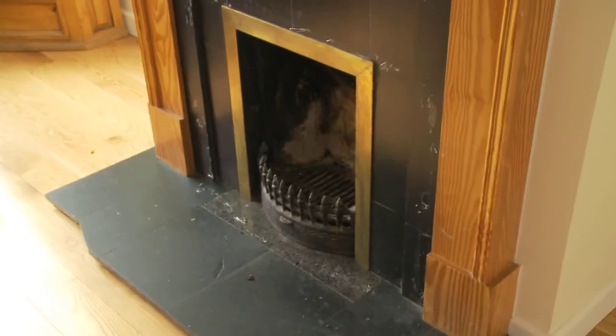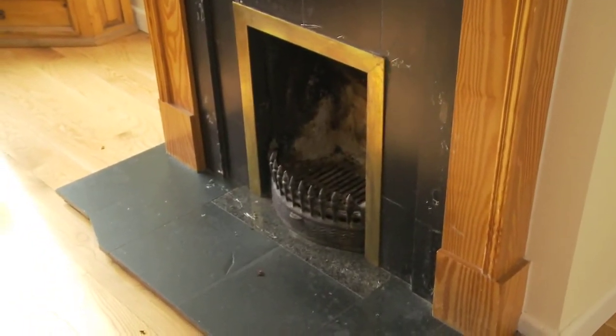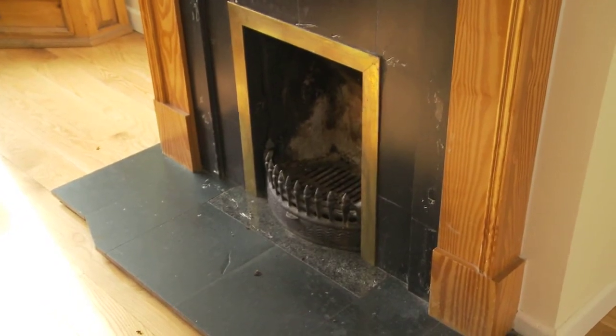Okay, so we're in the actual living room, the front room of the house, and that contains this open fire, open grate fire in the chimney breast. Now, from the software, DEAP, we are asked to input the main heating system and a secondary heating system. The main heating system here we'll be looking at in a minute, but it's radiators and it's operated off a gas boiler. The secondary heating system would be classed as this open fire in the grate, and it would be under the room heaters. So what we need to do is just record that that's here, take a photograph, and then we'll input that into DEAP.